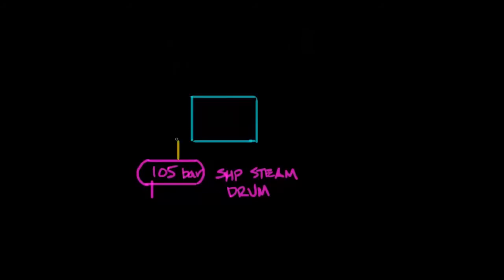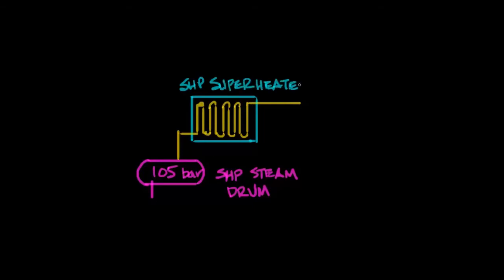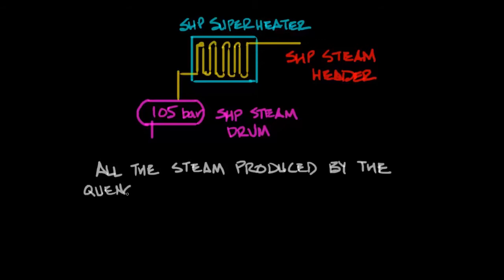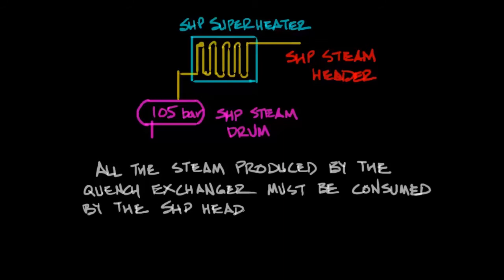After the steam drum there's a super heater also heated by the hot product. What comes out of the super heater is going to be very hot high pressure steam generally around 100 bar steam. All the steam that's produced by the quench exchanger has to be consumed by the super high pressure header. There's no place else for it to go.